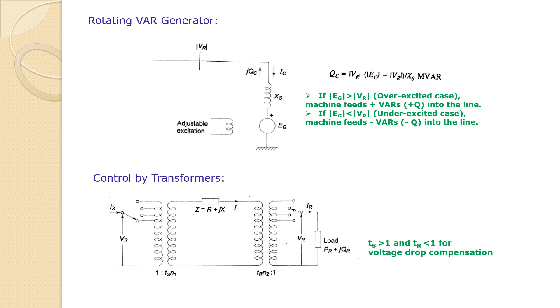The operation of a transmission line with a tap changing transformer at each end is shown in the figure. Here TS and TR are the fraction of the nominal transformation ratios, that is the tap ratio by nominal ratio. To compensate for the voltage in the lines, the transformer taps are set at off nominal values TS and TR. The value of TS is taken as greater than 1 and TR is less than 1 for voltage drop compensation. The normal tap setting range is usually not more than plus minus 20%. By adjusting the taps, the voltage can be controlled and hence Q can be controlled.